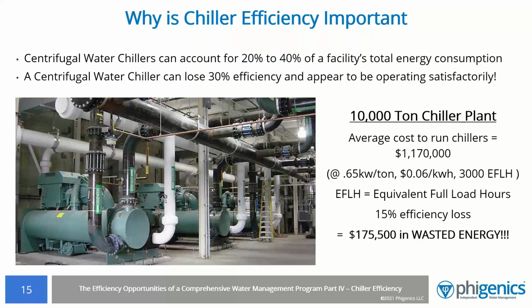EFLH is the number of hours a chiller system would have to operate at full load to equal the amount of cooling delivered by the system at a constant temperature over an entire cooling season. Of everything we have discussed so far in this presentation, if $175,000 in lost energy does not get your attention, then it's time to stop looking at the emails or texting and pay attention a little bit more.